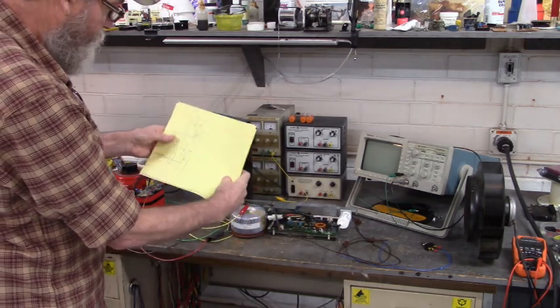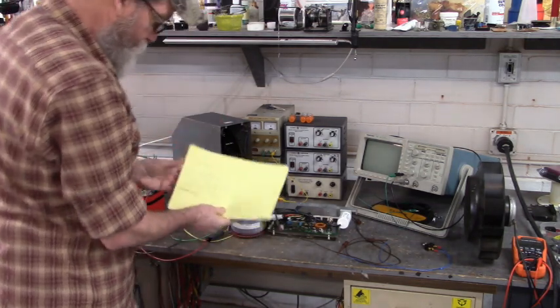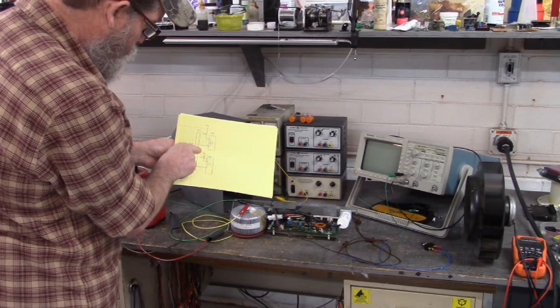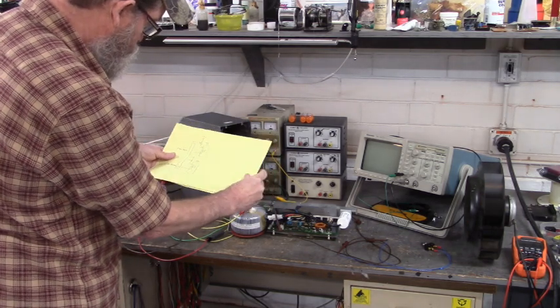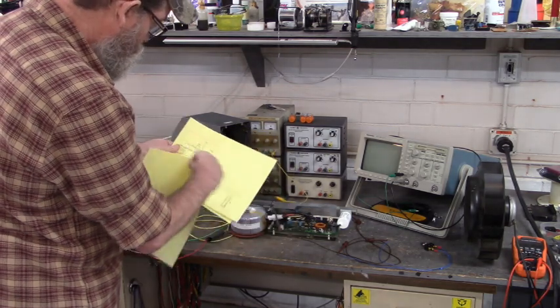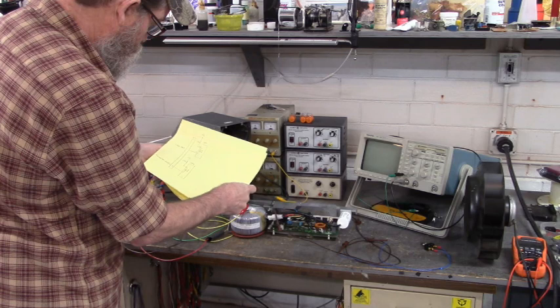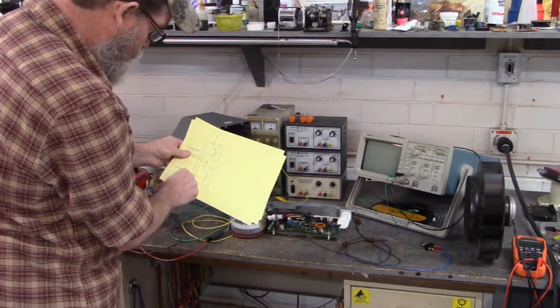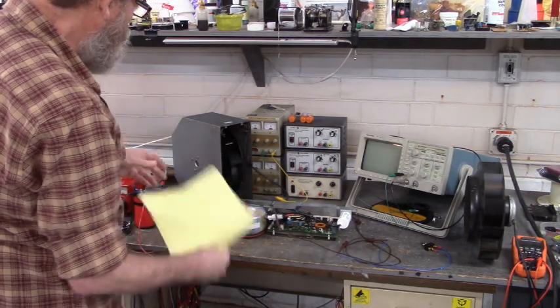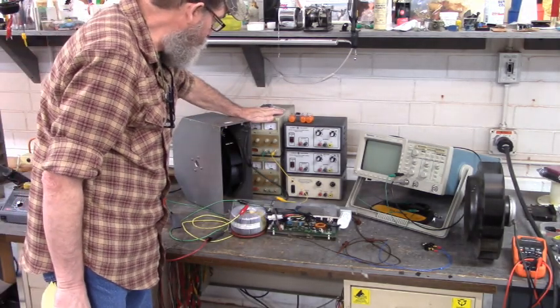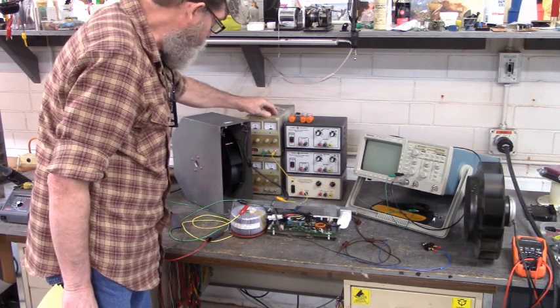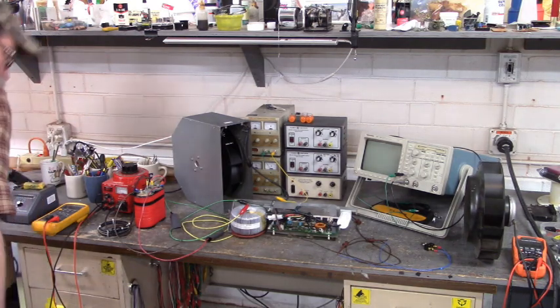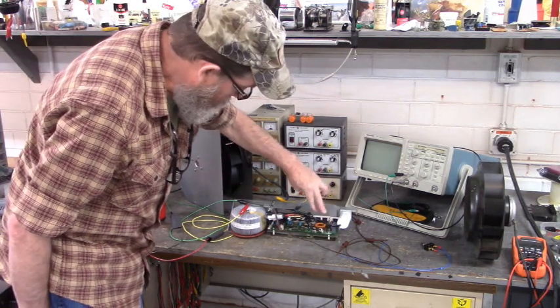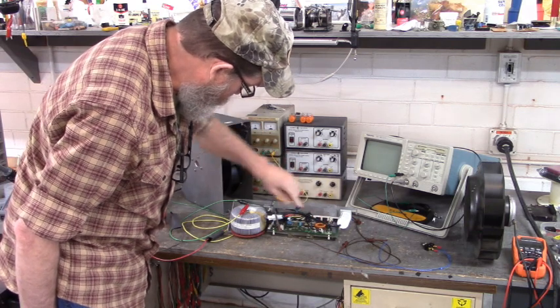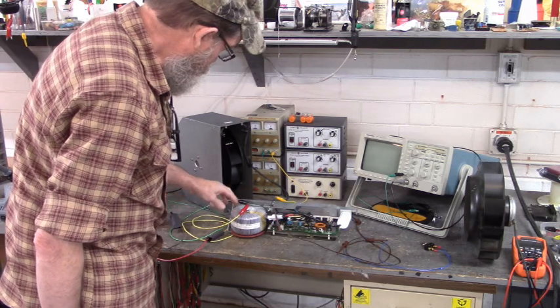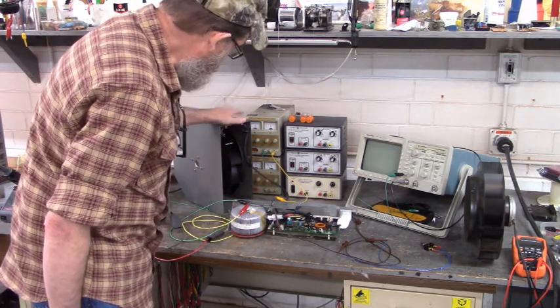To enable the blower motor to run, we have to apply 15 volts to the XA connector, pin 2, and then pull pin 3 to ground of that 15 volt power supply. We're creating our plus 15 volts for the enable signal from this power supply right here. There's a transformer right here that takes the output of this card into a 1-to-1 transformer, and the output of the transformer is applied to the blower motor.